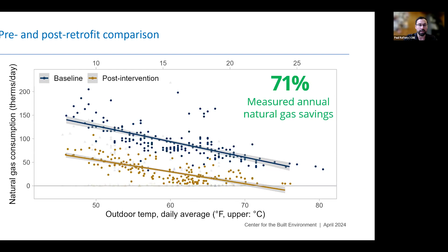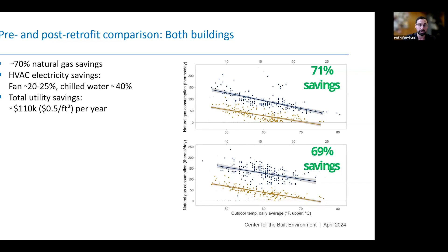We also had quite substantial electricity savings as well. These are a little bit harder to quantify because of the impact of the pandemic and the metering we had in place. But we saw about 20 to 25% fan energy savings and about 40% chilled water savings in these buildings too. In total, the energy cost savings, just the utility bill savings, are over $100,000 a year in both buildings from these combined efficiency measures.